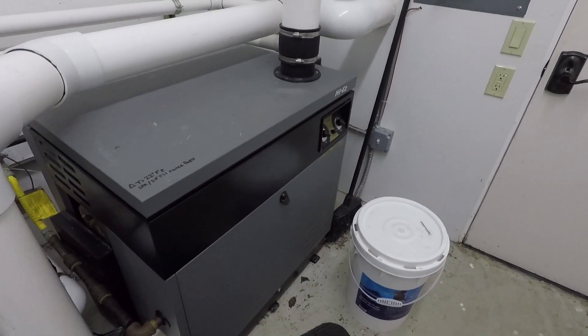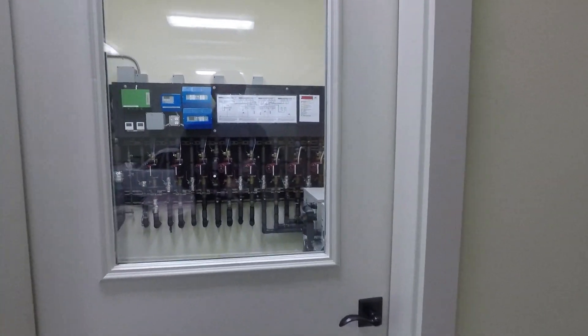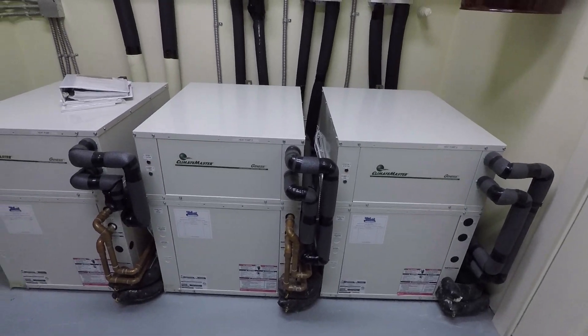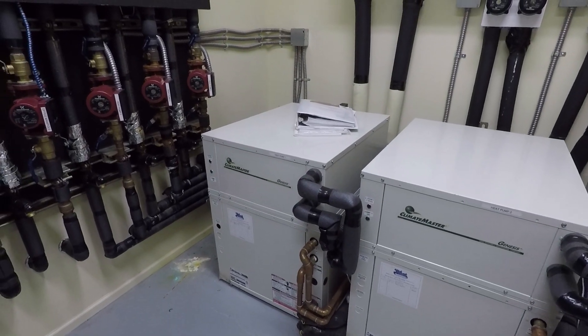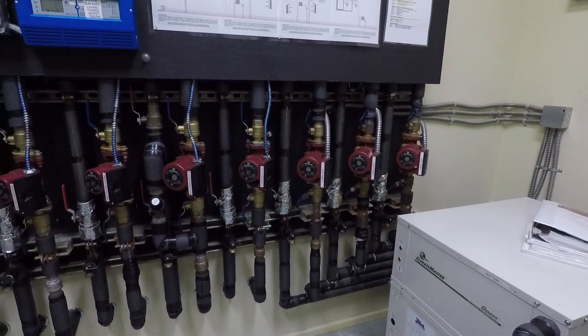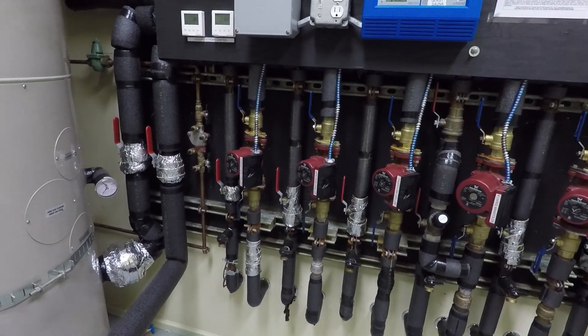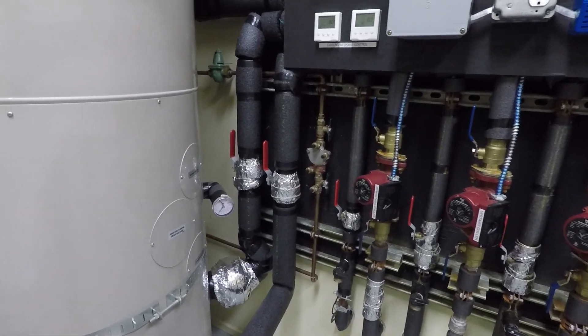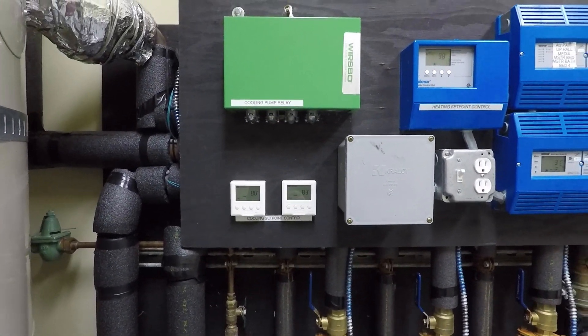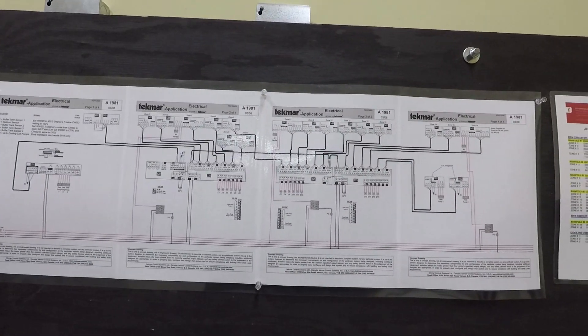This is a big gas-fired instant-hot unit. We have a big outdoor jacuzzi that stays cold all the time, but you turn it on and it's heated instantly. This is the utility room for the main house — a 7,000 square foot house. There are three Climate Masters that take the water out of the geothermal field and continue heating it; they're electric. Then there are eight Rehau distribution panels throughout the house, with eight pumps that circulate to those. Each panel has valves with zones — many zones throughout the house. You only want to go 300 feet maximum with your line per loop. There are also manifolds by Rehau throughout, and a tekmar control system that runs those. This is a schematic of the whole design and layout.